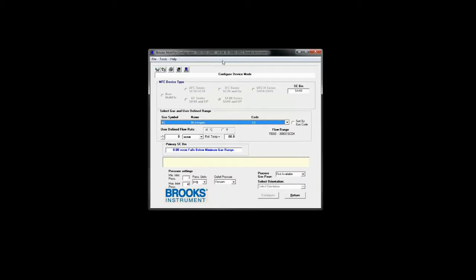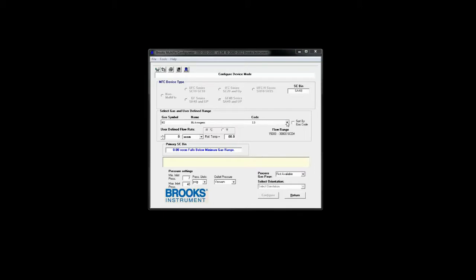This is where you can select a different gas, change device orientation, and modify the full scale flow rate. Note that whenever you change gases the flow rate of the device may change due to differing gas properties.